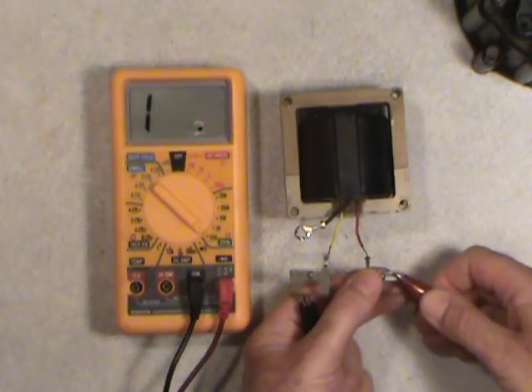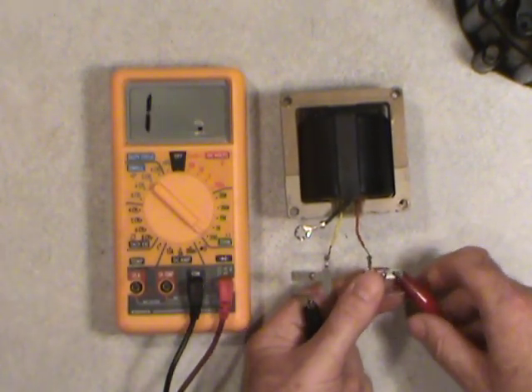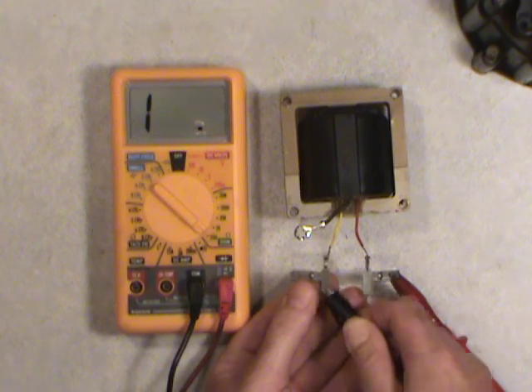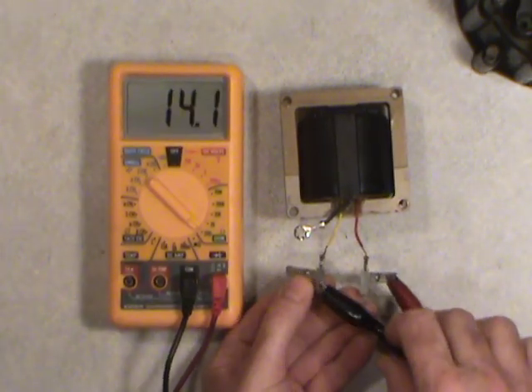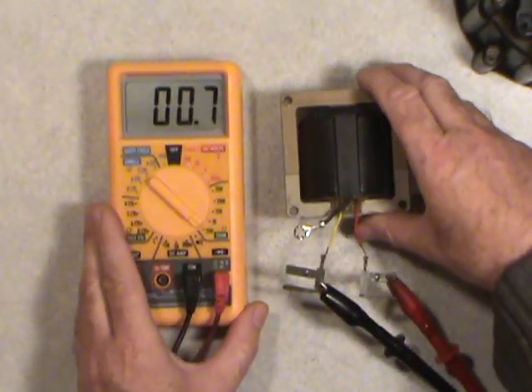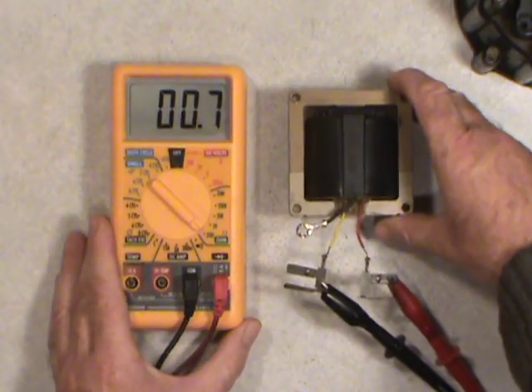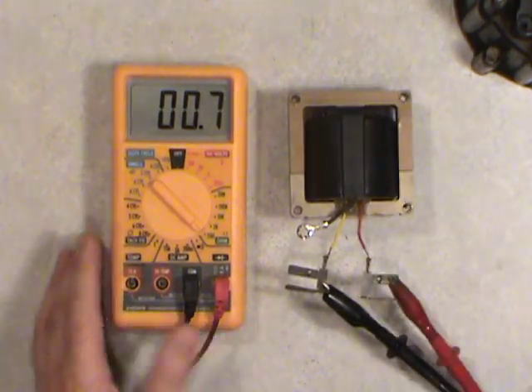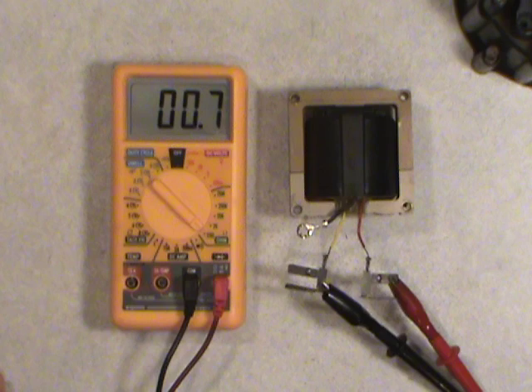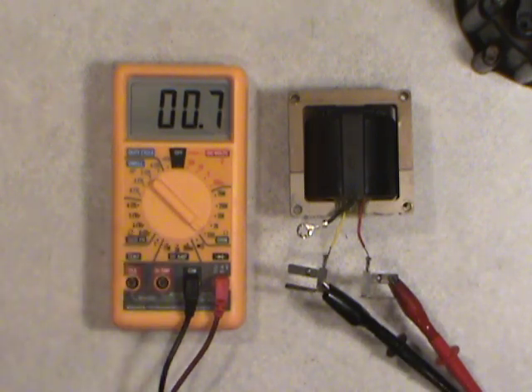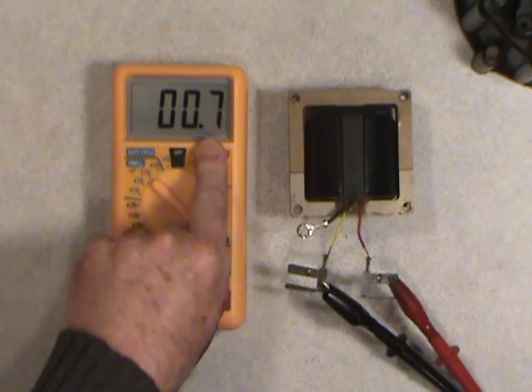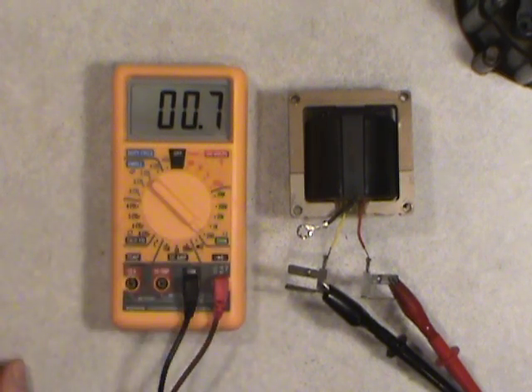Okay, now we'll get back into things here. Grind it in there, get a good connection. And another good connection like so. Make sure everything stays put. Now we're getting 0.7. Remember, we're at 0.3 for the meter's calibration, so we have to subtract 0.3 off of that. Okay, so then there's 0.4. That's our low ohms reading.